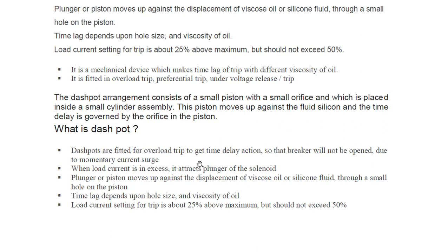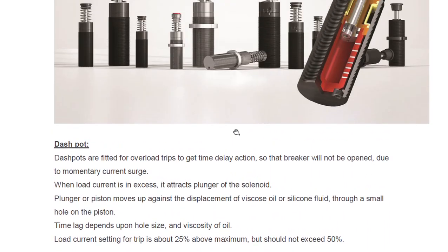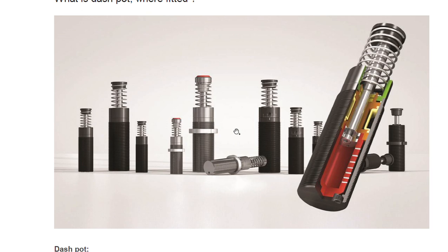To summarize: dashpots are fitted for overload trips to get time delay action so that the breaker will not open due to momentary current surges. When load current is in excess, it attracts the plunger of the solenoid; the piston moves up against the viscous or silicone fluid through the small hole. Time lag depends on hole size and oil viscosity. Load current setting for trip is about 25 percent above maximum but should not exceed 50 percent. It is a safety device with its components as discussed.